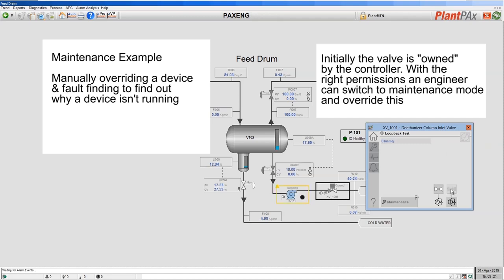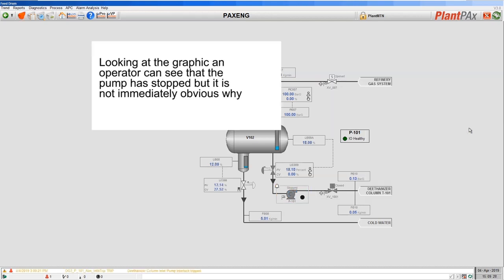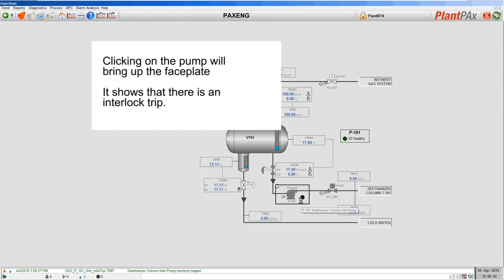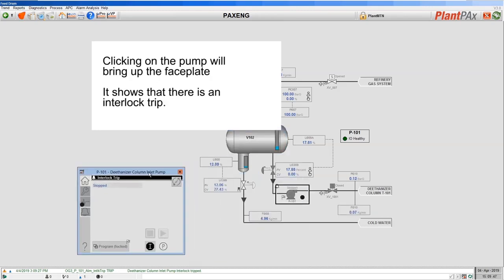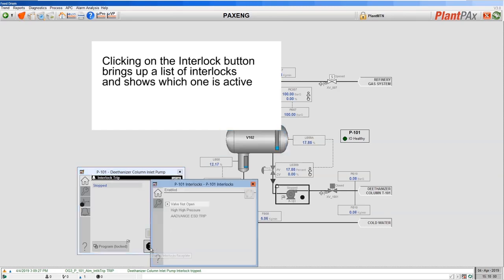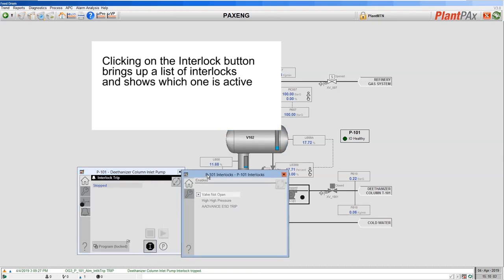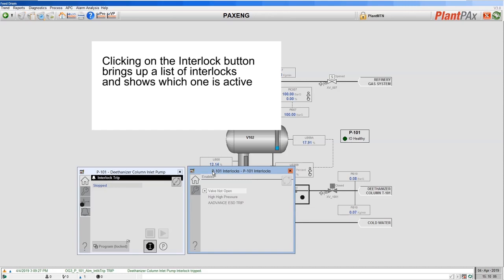The device is now in maintenance, and from the main faceplate I now have the ability to command the valve to close. Now that we've commanded the valve to close, we can see that the pump has stopped. As an operator, when I come to this graphic I can see the pump is stopped but it may not be immediately obvious why. Using the standard features in the library, I can bring up the faceplate for the pump and immediately see that there's an interlock trip present — that's what tripped and stopped the pump and is preventing it from running.